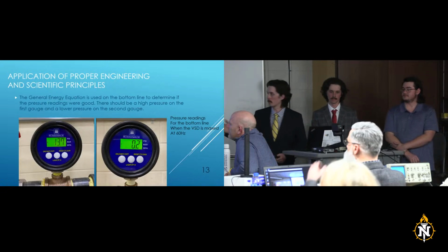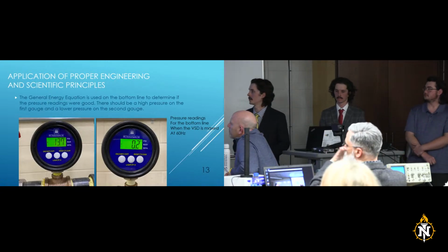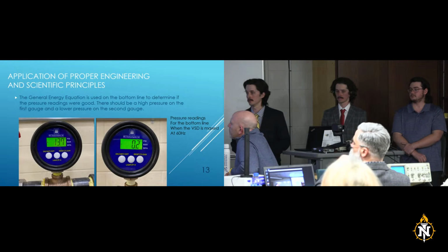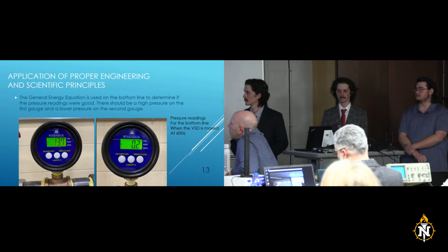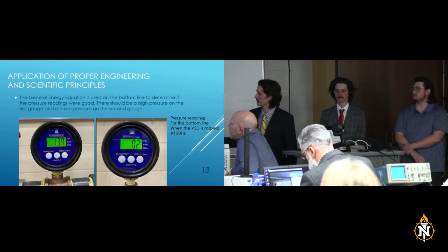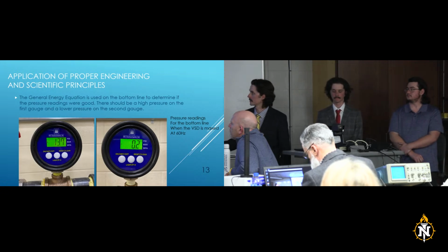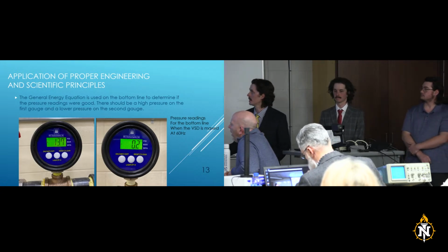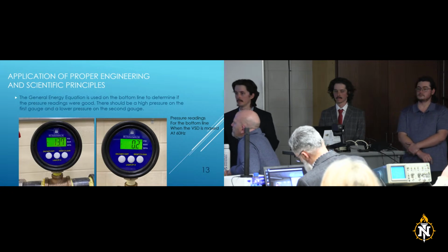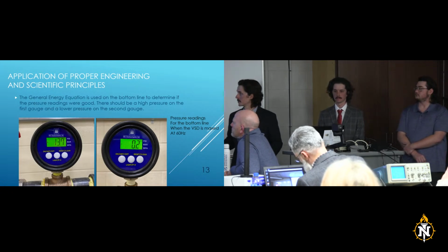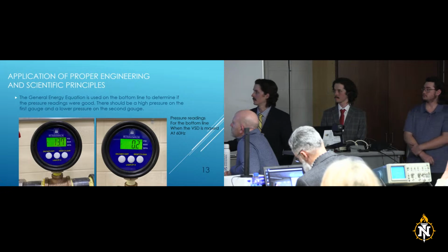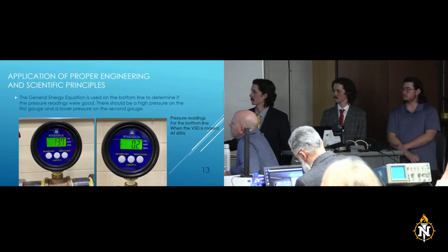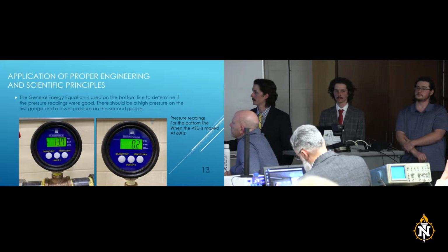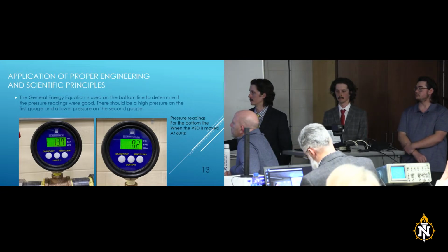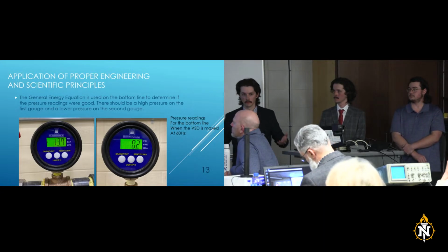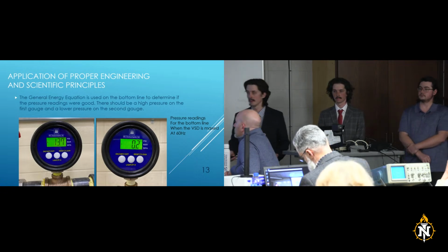So here are two of our pressure gauges. These are the pressure gauges on the bottom line, which we are using to find minor and major losses. Our first pressure gauge gives a reading of 13.7 psi, and this is when our variable speed drive is maxed out at 60 hertz. And when the water runs through the line, we get a reading of 0.2 psi on our last gauge, so the losses are quite significant.